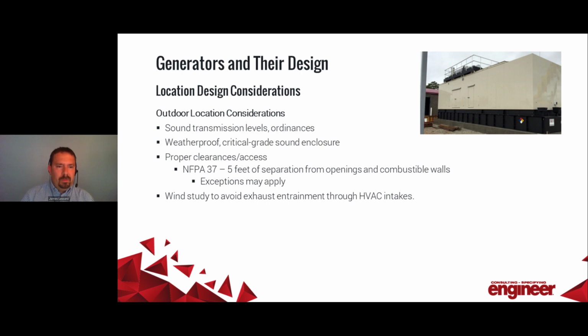Ways to address that would be a critical grade sound enclosure system, and a weatherproof enclosure when you're outside anyway. There may be other ways to mitigate the sound, and that's where an acoustical analysis would be warranted if you're having trouble meeting a specific ordinance requirement. Again, proper clearances around the generator and access applies whether you're inside or outside.